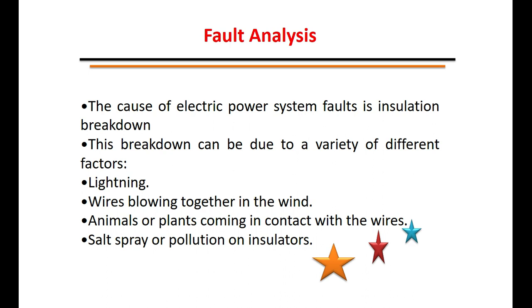The cause of electrical power system faults is insulation breakdown. There are many reasons for insulation failure because of which a fault occurs in the system. This breakdown can be due to a variety of different factors: lightning discharge on overhead transmission lines, wires blowing together in the wind, short-circuits, plants coming in contact with wires accidentally, and salt spray or pollution on insulators.